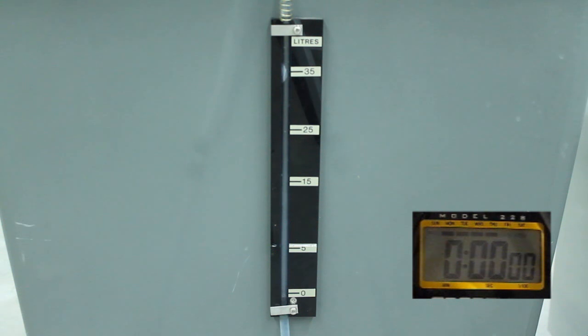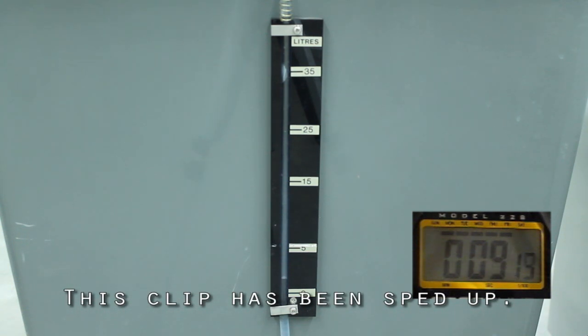Start the timer when the water line reaches 0 liters and stop it when it reaches 25. The volumetric flow rate is 25 liters divided by the measured time.